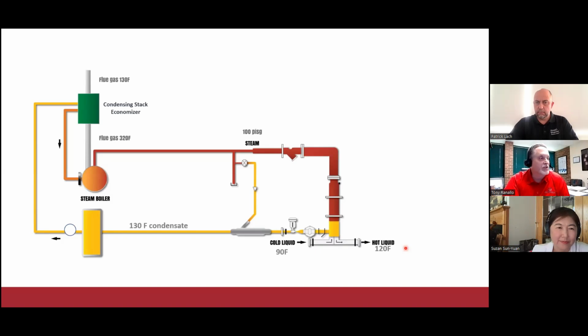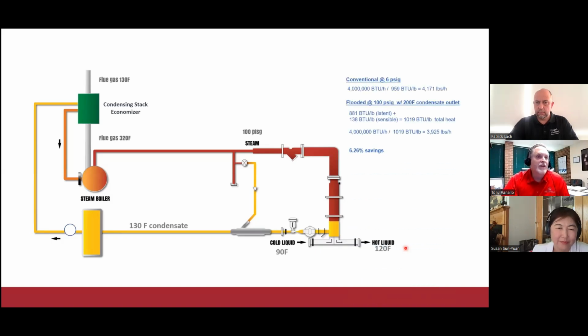Let's take a look at what makes a vertical flooded heat exchanger a good choice for district type systems. If we look at a conventional heat exchanger versus the equivalent flooded heat exchanger and say that in this first example, we're looking at a 4 million BTU process load. If you look at your steam charts, we're looking at about 959 BTU per pound of latent heat. So we need about 4,171 pounds of steam to satisfy that load.